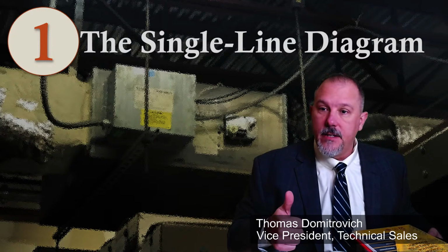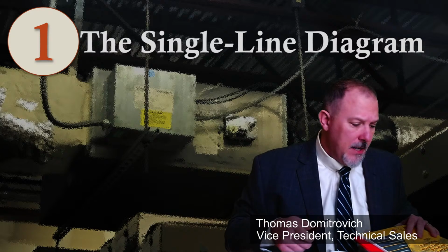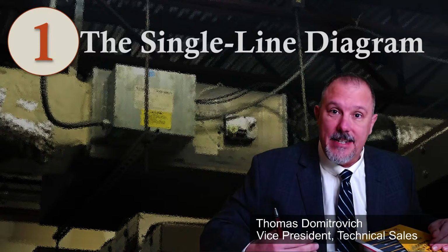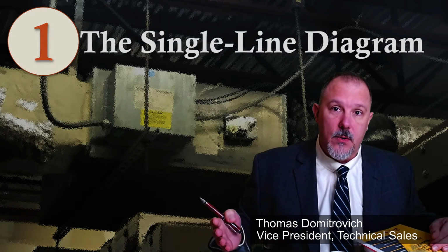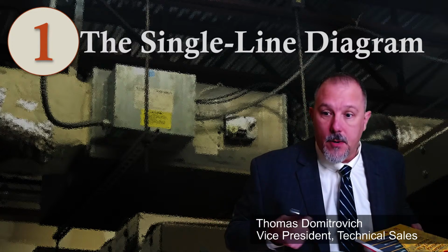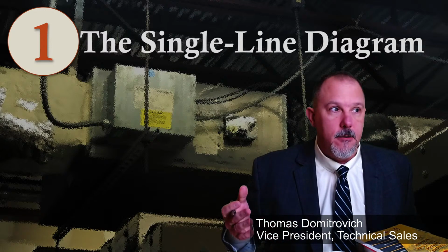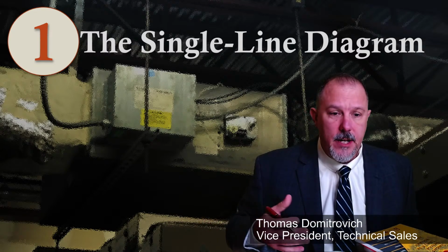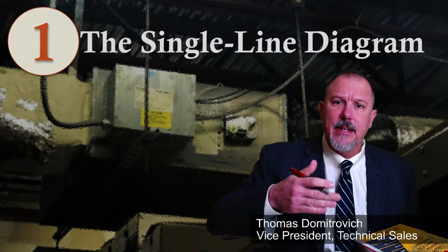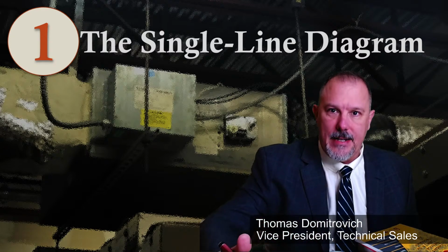A lot of people forget about the importance of the single line diagram. The single line diagram plays an important role in electrical safety, but just like I did yesterday, it falls off of the table. It's the last thing that's done. Hopefully you had to have a one line diagram probably to bid a job or specify, show the layout of the diagram and show your power distribution system. But quite often, probably more often than not, it never gets updated.